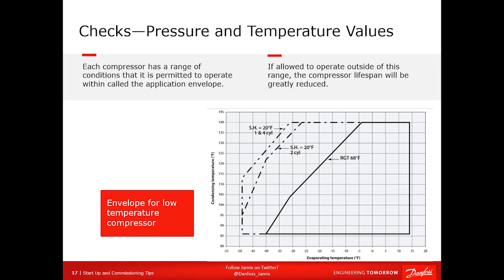Now, another thing nobody knows exists really, except for engineers and me, and some other people, is the application envelope. When people ask me, Jamie, what should I set my pressure controls at? I answer whatever the application guideline or the application envelope tells you to, and they give me a blank look. I said, it's in the guide, look at it. Whether it's Bitzer, Copeland, Danfoss, any of us, we all provide these diagrams, and they're very important because this is the operating envelope that the compressor can operate under and live to tell about it.